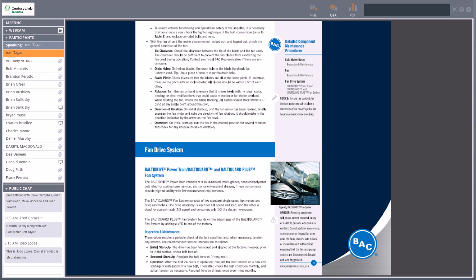Fan drive system, like I said, there's usually three different kinds. You have your belt drive, which historically Baltimore Air Coil has promoted. It's their opinion that it's an easier fix if you do have a problem. One of the things that we all know is when cooling towers go down, they don't always go down at 9:30 on Monday morning. Sometimes they go down at 5 o'clock on Friday or over the weekend. So keeping a spare belt on hand is relatively an inexpensive piece of inventory, or you could also get by through the weekend with 4 or 5 belts from the auto parts store if you had to.